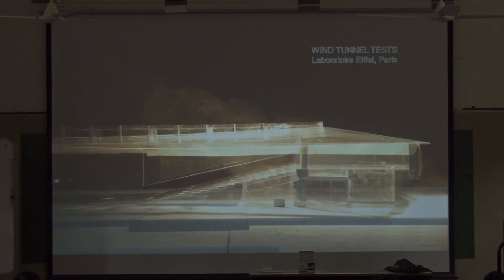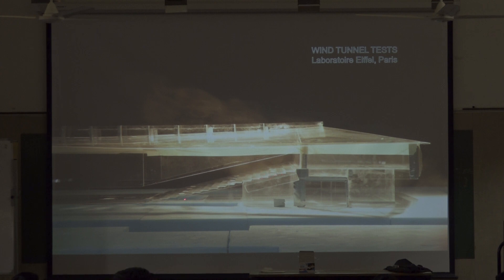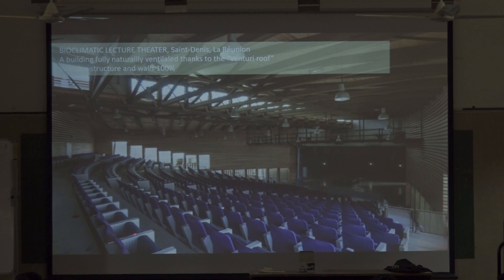A smoke test was used to verify that the shaft works: the wind comes from one direction, and the smoke is sucked up through the roof. In terms of design, there are small holes to have porous seats, and even the back of each seat is fitted with a mesh to increase air movement around occupants. Every detail is important in this lecture theater.